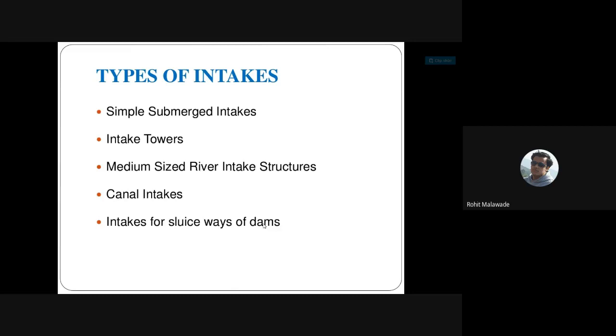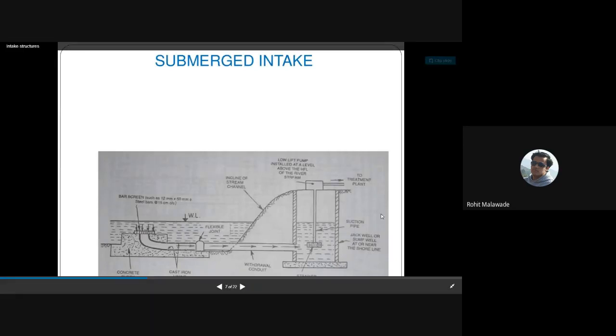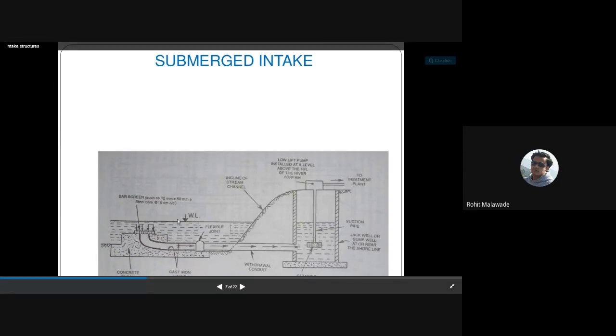The types of intake structures are: simple submerged intake structure, intake towers, river intake structures, canal intake structures, and canal intakes with sluice gates of dams. In a submerged intake structure, the intake pipe is constructed over the inclined stream channel. The intake pipe should be fixed with bar screens and a strainer is located at the pipe entrance.